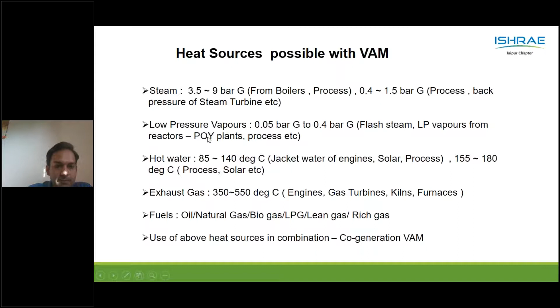We can also design vapor absorption machines using a combination of heat sources. That is, steam cum hot water or exhaust cum hot water VAMs are also possible. Further, various metallurgies are possible. These are the water qualities of the normal water or the sea water applications. The major criteria you can see is the chloride and the sulfate levels. For the difference between the two, 2300 and 18,000, parameters of sea water we can use in a VAM.